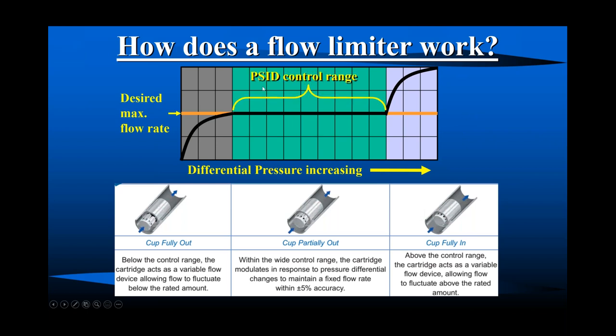And that is a PSID control range: lowest pressure, highest pressure, and where it can modulate. Before that, it's not doing anything; something has authority here, probably the control valve if it's a modulating application. And if it does bottom out, and it shouldn't, but if it did, it becomes a fixed orifice as well.